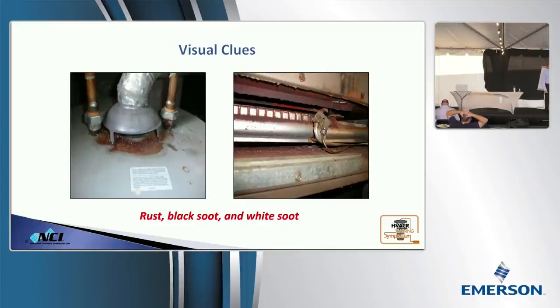Check the draft hoods. Rust is one of those things that we see a lot and we think it's normal. Have you guys ever wondered why some equipment is perfectly clean? Other equipment, you'll go in and it's got an inch of rust sitting in the bottom of it. Why? Because the one that's clean, the flue gases are probably leaving the equipment. The one that's rusting, the flue gases are spilling. And that's condensing inside that furnace.